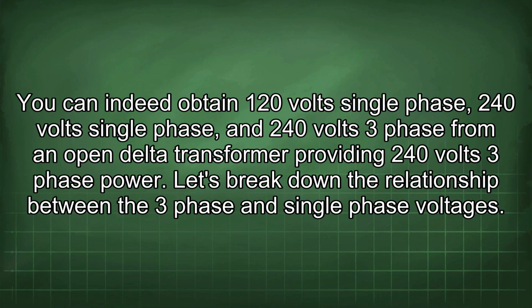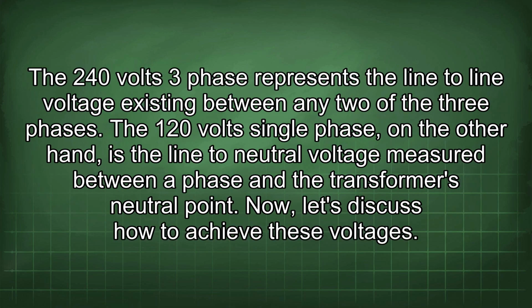You can indeed obtain 120 volts single phase, 240 volts single phase, and 240 volts three-phase from an open delta transformer providing 240 volts three-phase power. Let's break down the relationship between the three-phase and single-phase voltages. The 240 volts three-phase represents the line-to-line voltage existing between any two of the three phases. The 120 volt single phase, on the other hand, is the line-to-neutral voltage measured between a phase and the transformer's neutral point. Now let's discuss how to achieve these voltages.